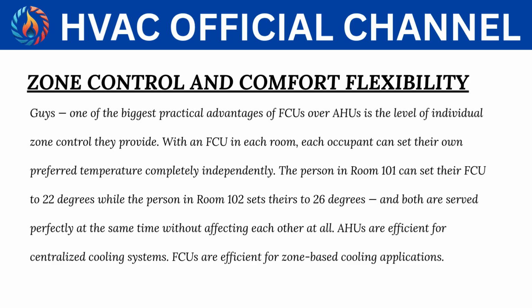The person in room 101 can set their FCU to 22 degrees, while the person in room 102 sets theirs to 26 degrees, and both are served perfectly at the same time without affecting each other at all. AHUs are efficient for centralized cooling systems. FCUs are efficient for zone-based cooling applications.